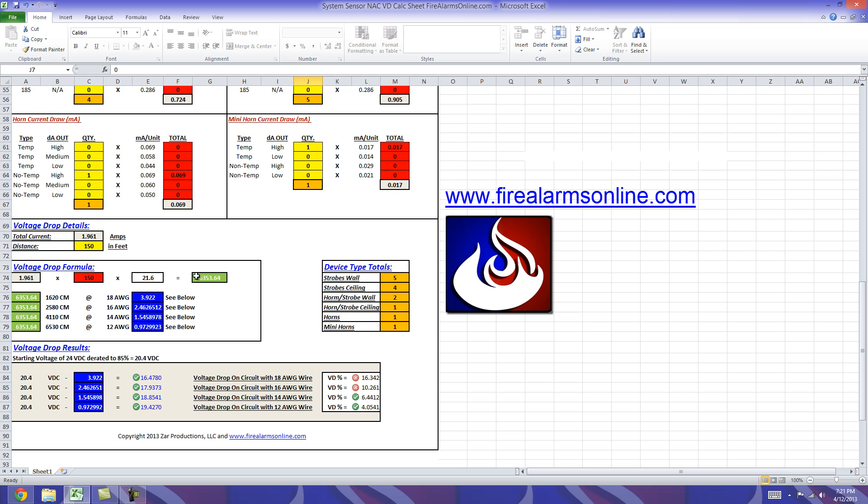So once again this number moves down to here and now we're going to divide that number by the circular mills and that gives us our voltage or our volts drop for the circuit. So we have 3.922 and so on down here for each particular wire gauge.